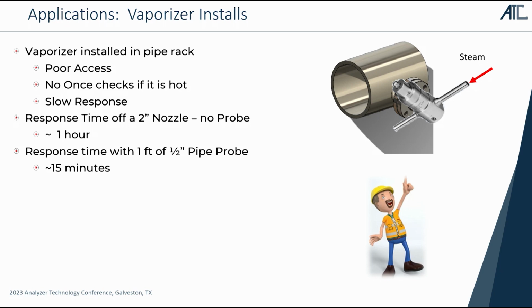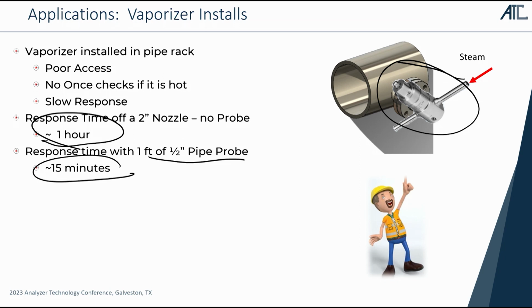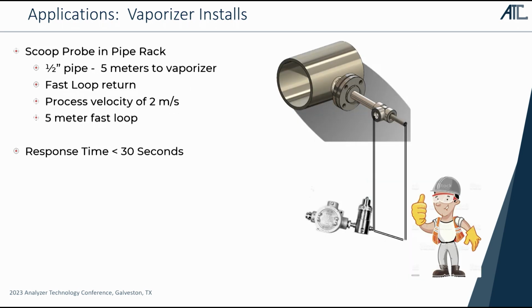And so when we have vaporizers up there, and they're coming right off of a pipe nozzle like this, they can have a lot of time delay before we get into the vaporizer, and really slow response times. Like I said, I went through the calculations. On a 2-inch pipe nozzle without a probe, you probably have an hour of time delay getting into the vaporizer. If you add a probe that's about 1 foot long of 1/2-inch Sched 80 pipe, you might be down to 15 minutes. Big time delays up there. These vaporizers only run at a few milliliters a minute. We can put in something like a scoop probe horizontal on that same upper pipe run. Run 2 pieces of 1/2-inch tubing down. Put that vaporizer down at grade now. Put that vaporizer someplace where there's a platform where a guy can stand on it and actually do maintenance on it.